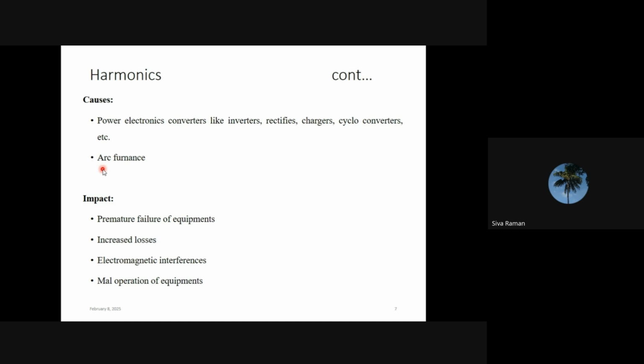In addition to this, there are some other devices that will also produce harmonics, but it is not a normal operation, it is an extreme operation. We know a transformer is a linear equipment, but the transformer also will produce harmonics when the transformer core is saturated. The moment the transformer core is saturated, the transformer will produce harmonics. Okay.